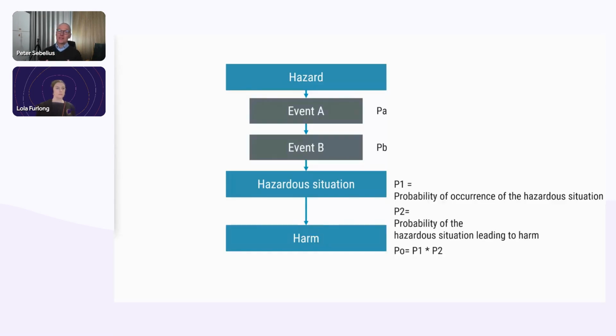And some of you have read the standard well. You have seen a similar flowchart in the standard, and it shows how a hazard leads to various events with their own individual probabilities, in this case PA and PB, as you can see here. And that in turn results in a P1, which is the probability of occurrence of the hazardous situation. And when you have estimated the probability of that hazardous situation leading to harm, that's the P2, you get to PO, which is the probability of occurrence of harm.